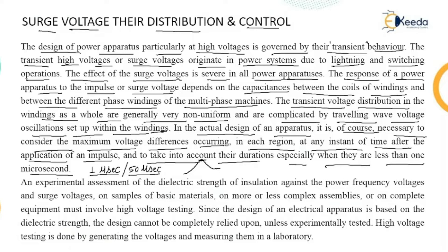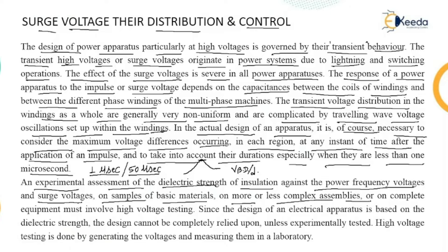These time periods are defined by standards, such as 1µs/50µs or 1.2µs/50µs. Dielectric strength means the breakdown voltage per unit distance. An experimental assessment of the dielectric strength of insulation against power frequency voltages and surge voltages — on samples of basic materials, complex assemblies, or complete equipment — must involve high voltage testing.